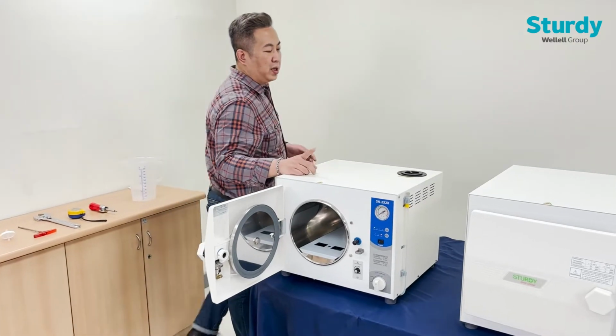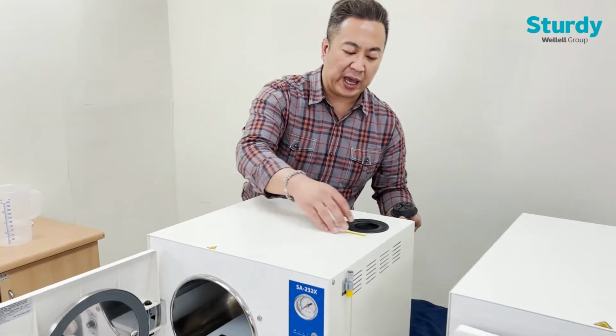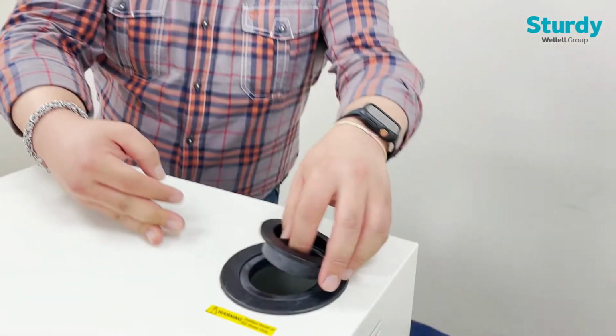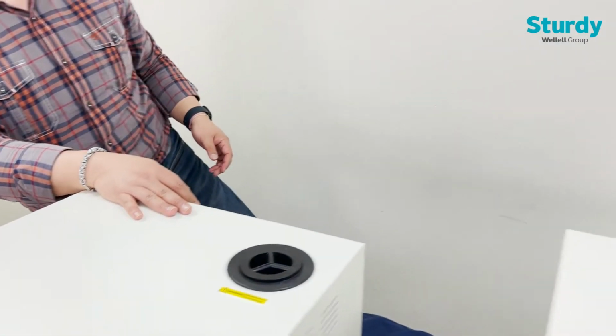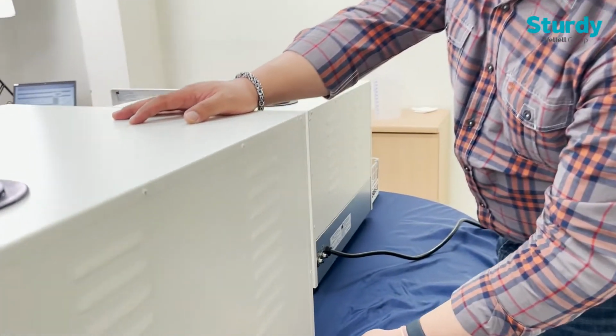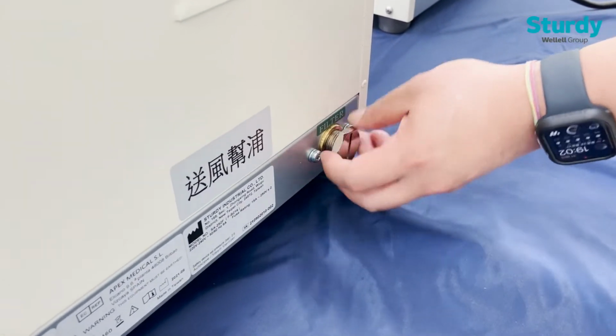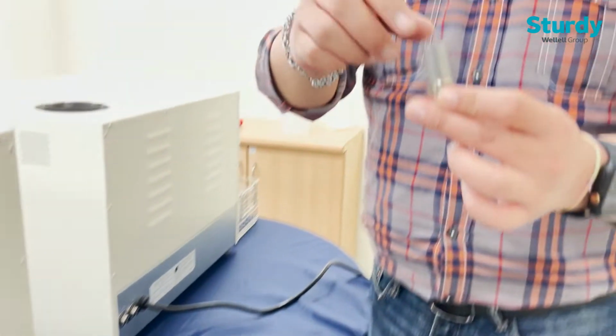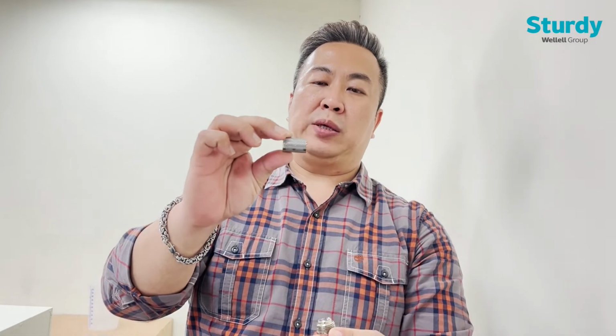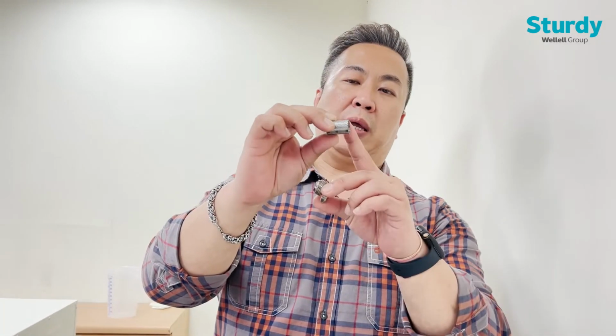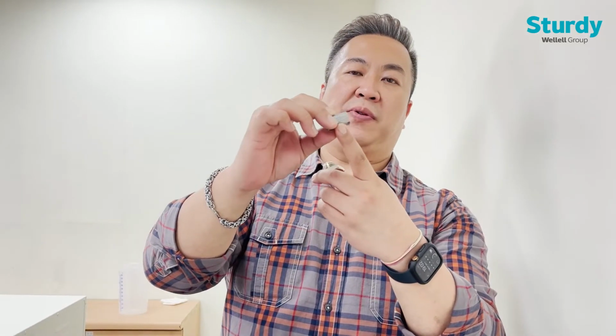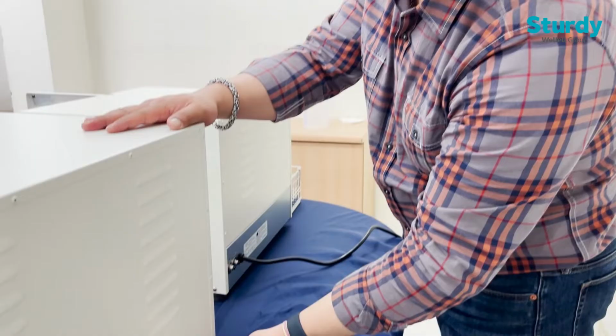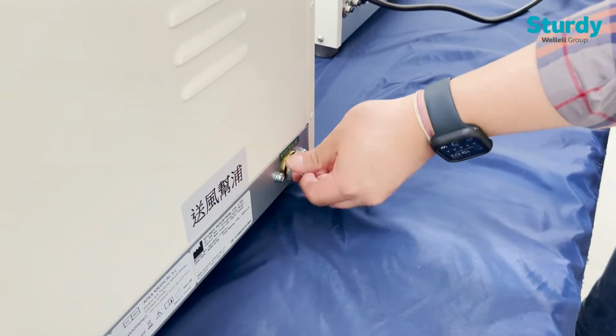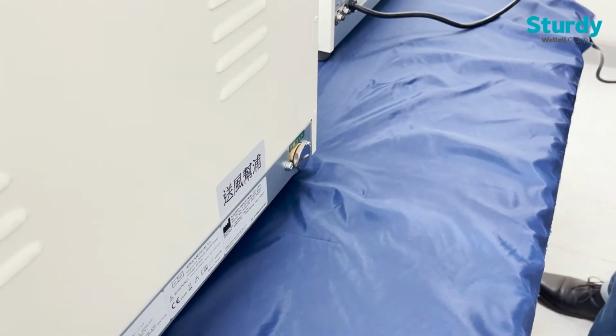There are 2 filters. One is the water filter, which is located at the bottom of the water tank. Two is the drain filter, which is located at the back of the machine on the bottom. Using an instrument, we unscrew it and remove the filter. This is the actual drain filter, and we can use water and a soft brush to clean all the dirt and residue on the filter. Once that's cleaned, put it back onto the screw base and simply replace it into the machine. That is the weekly maintenance that needs to be carried out.